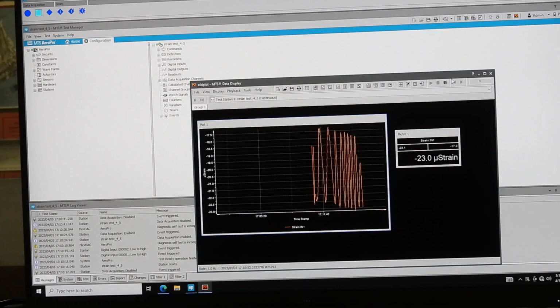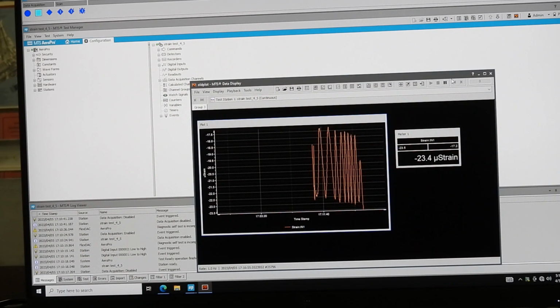But what channel do we use to do that? Digital output? Well, I go analog on that side, if you have enough analog, like the one that we have hooked up. We just tell it to send out a voltage, and that's in the procedure editor, right? That's where you'd put in another one. You can make a program-only channel and just name it something, like FlexDAC enable, disable signal, or FlexDAC control.